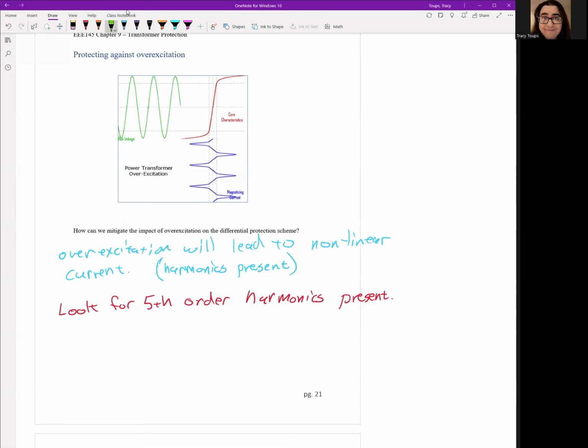If we're in the saturation region, we need to make sure we don't trip the 87 immediately and cut customers off. Typically, overexcitation saturation is a gradual thing. It doesn't happen on the flip of a switch. Your system is running normally, then it's getting a little too hot, a little bit too hot, maybe some LTCs are operating somewhere, and you slowly creep into it. It's typically not just on-off; you don't go from 100 kV to 200 kV. So if we start entering a saturation region, we don't want to trip the differential immediately, because then we'll lose a bunch of customers. So what we do is we activate a restraint.